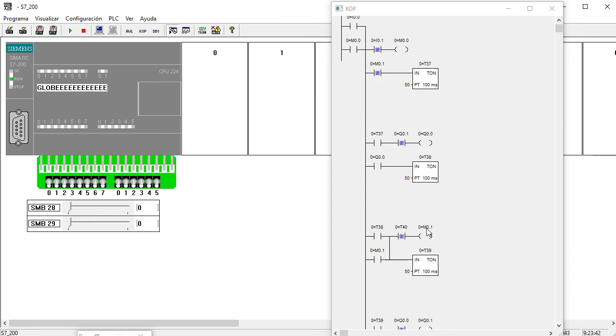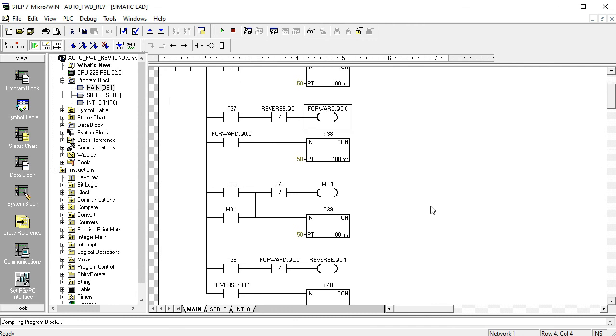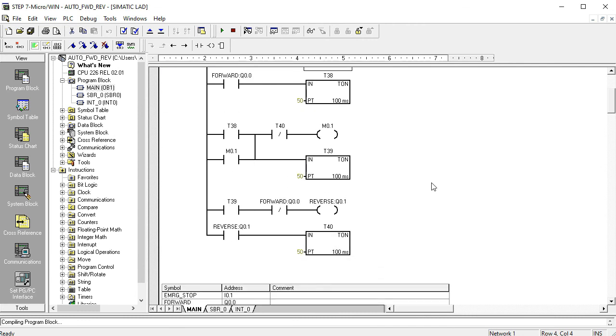The make contacts are connected at every step. After five seconds, Forward turns on; after five seconds it turns off; after five seconds Reverse turns on; after five seconds it turns off; then after five seconds Forward turns on again. This is the automatic processing system — step-by-step processing is our main programming sequence for the S7-200 PLC automatic Forward/Reverse system, and this processing continues indefinitely until stopped. The Stop button will stop it instantly — that's the facility of the stop button in this programming.